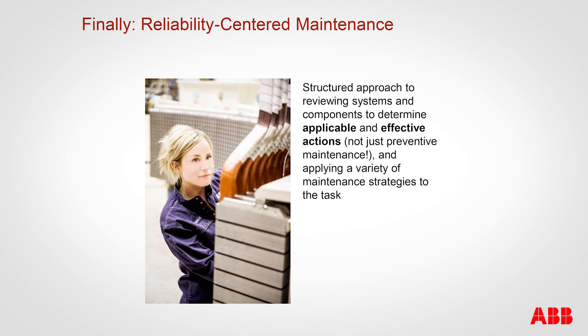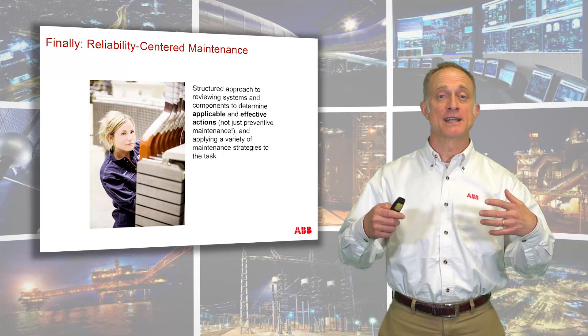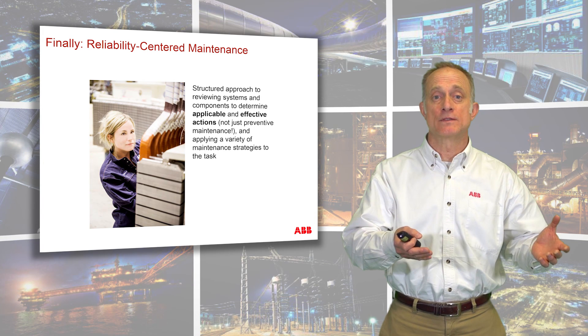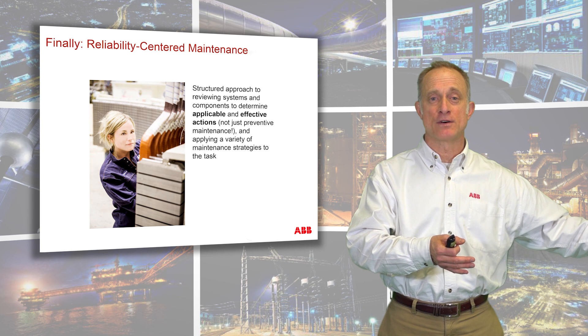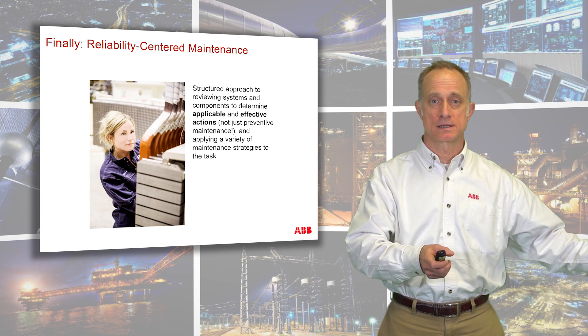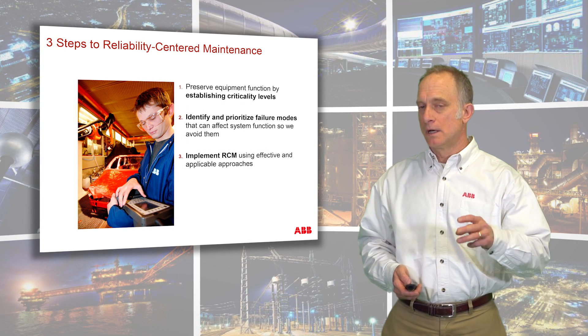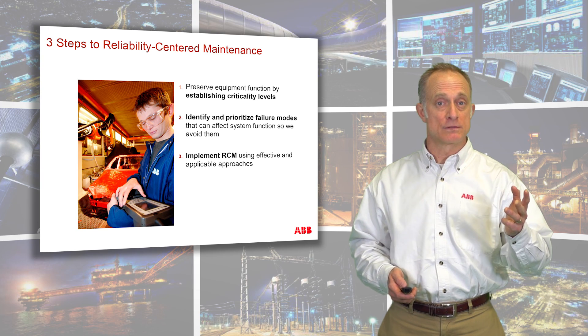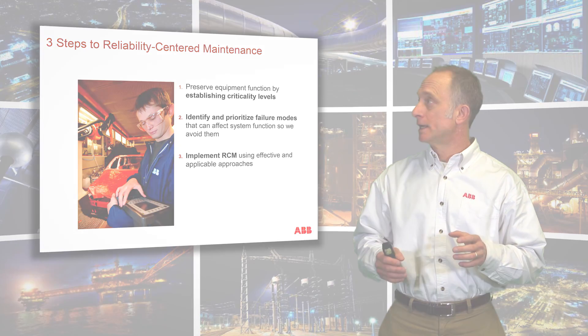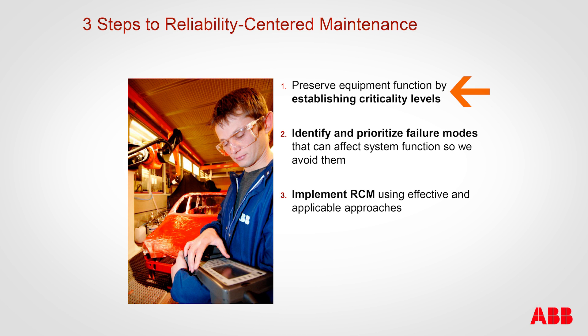Even reactive maintenance — or a strategy might be to not choose any maintenance approach at all. The right strategy might be to just let a piece of equipment run to failure if it's low cost and you have a hot spare. Maybe it's just too costly to try to touch that on a regular basis — let it fail. So the three main steps to effective reliability-centered maintenance are: first, preserve equipment functionality by establishing criticality levels; second, identify and prioritize failure modes; and third, implement reliability-centered maintenance by choosing the correct approaches.